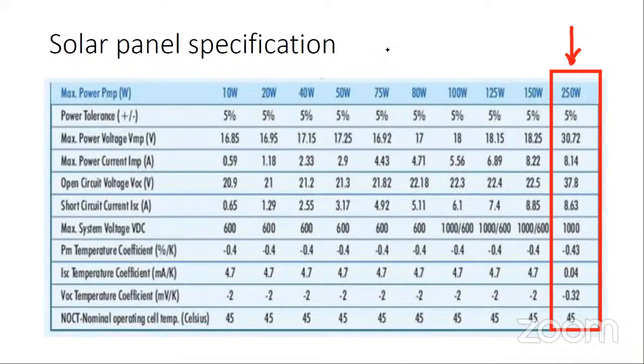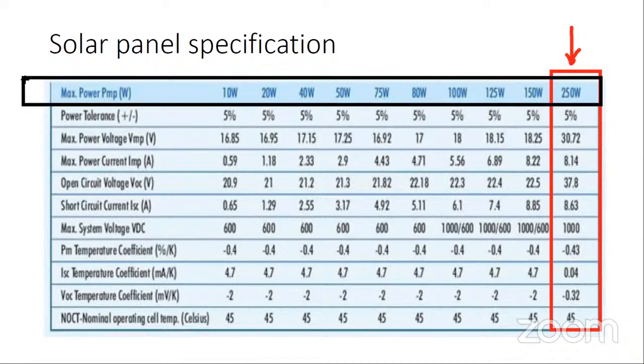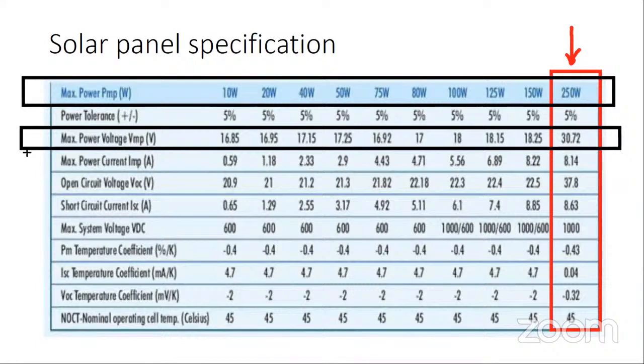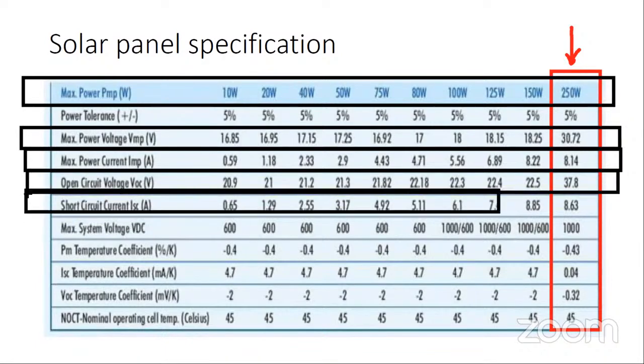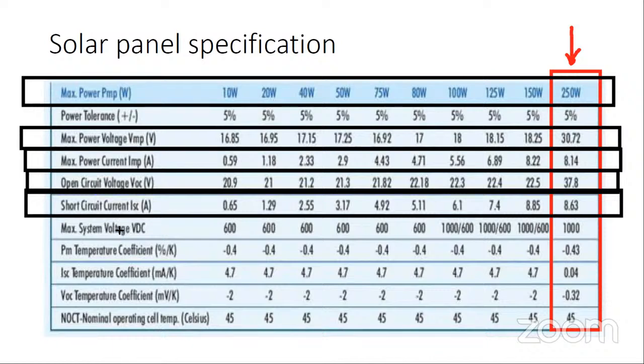The first condition to see is what is the maximum power, 250 watt. Then what is the VMP? What is the IMP? Then what is the VOC? Then what is the ISC? Then VDC, as you already know, 1000 volt. These are the main things one must look at: maximum power, VMP, IMP, VOC, ISC. All these five factors have to be clearly understood. So if you look for a 250 watt panel, these are the things you need to note down before starting a design. You also can note it down.